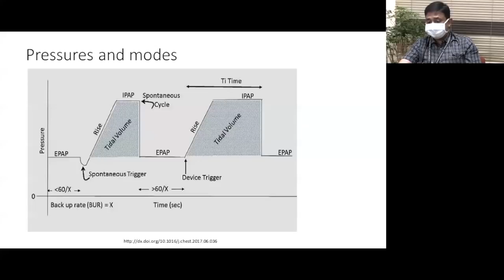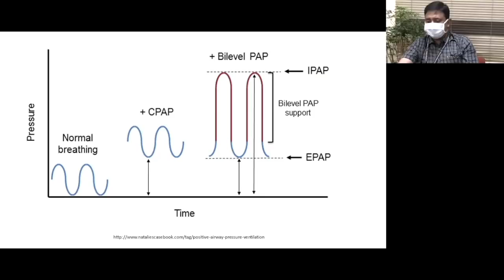Now, understanding it in an easier way: breathing is not static. There is an inspiration and expiration. Again, time on the x-axis, pressure on the y-axis. What we see in the first picture at the left bottom is normal breathing. When we put a patient on CPAP, the baseline EPAP is elevated, and there is tidal breathing going on top of that. When we give bilevel positive airway pressure, we increase the pressure support, or the difference between the IPAP and the EPAP, and we are able to give a higher pressure during inspiration and maintain the EPAP during expiration.